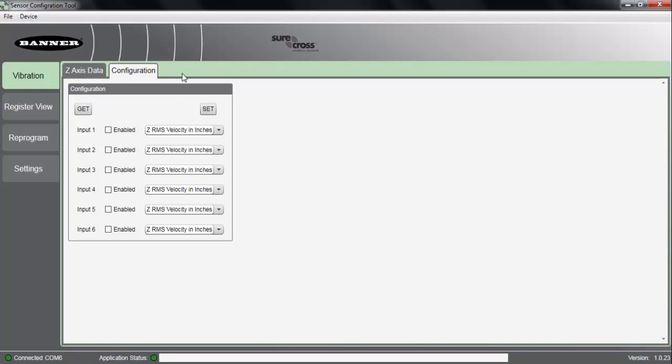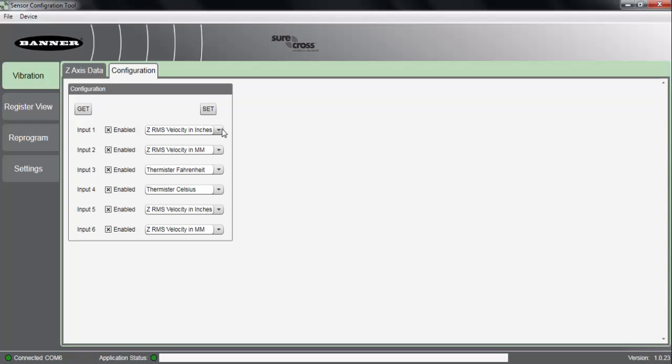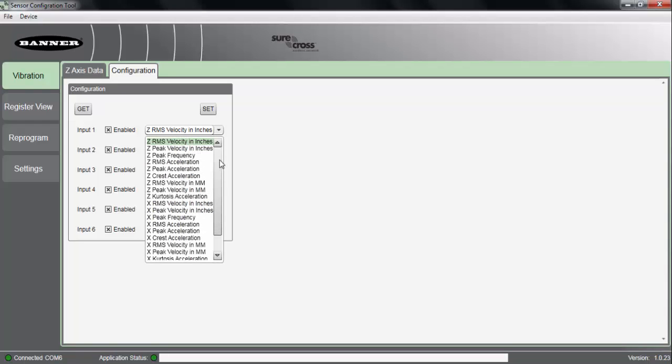First, within the configuration tab, we have the ability to change which registers are actually being pulled back when we're using the vibration temperature sensor in a wireless system. So by default, we're pulling back information in velocity in inches and millimeters per second as well as temperature. But the vibration sensor is gathering much more data than this.